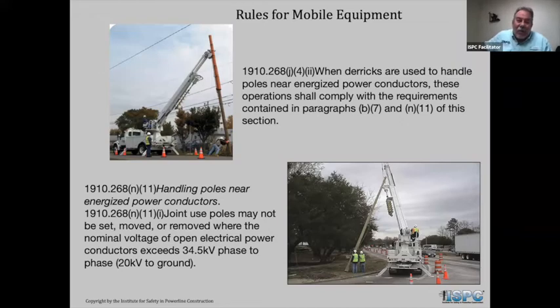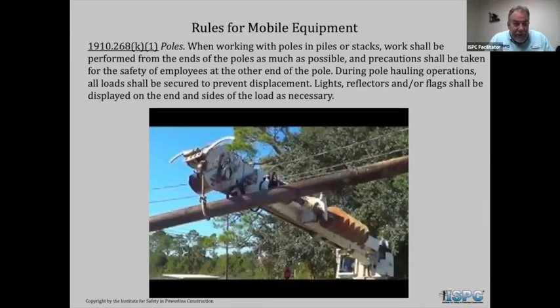Handling poles. Wood is a conductor. We've done a lot of conductive wood tests just to show how many volts a pole can actually carry. Creosote poles, usually a little bit lower voltage, but our new pressure treated poles, they're usually pressure treated with some kind of chemical that has a metal in it, which makes the pole now very conductive. So anytime setting a pole, it should have at least some cover on it. I would never let any of my employees set a pole in line without covering energized conductors. All right, moving on.